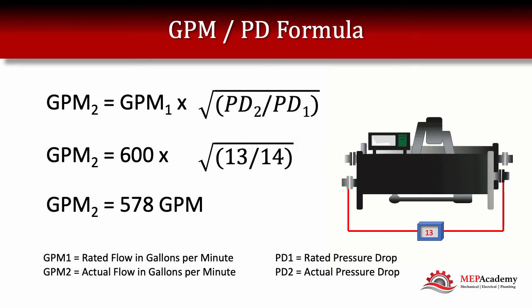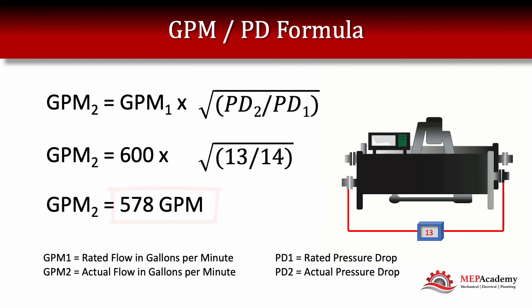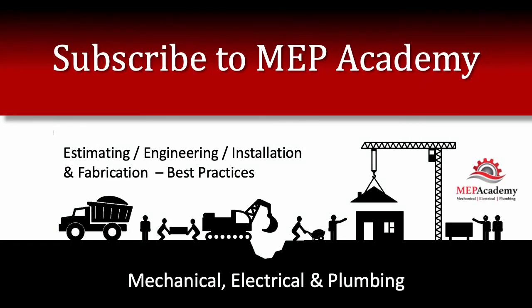All we have to do at this point is the math. Doing the math, we come up with 578 GPM. So our 600 GPM at 14 feet pressure drop rated condition is now only flowing 578 GPM due to the decrease in pressure drop. A decrease in pressure drop equals a decrease in GPM. Subscribe for additional videos — we will be covering mechanical, electrical, and plumbing estimating, engineering, installation, and fabrication best practices for mostly commercial construction and some residential.